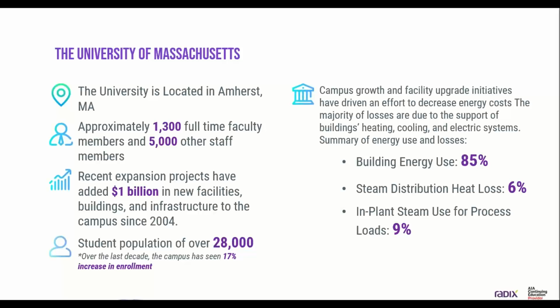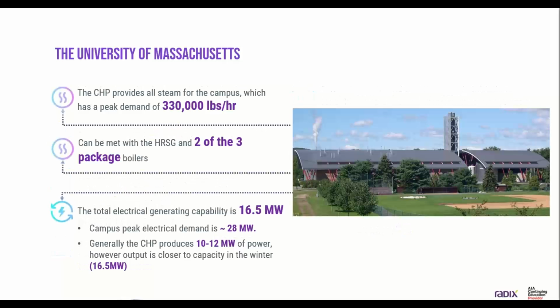So the campus growth and facilities initiatives have driven an effort to decrease energy costs. Major losses here are really due to the buildings on campus - heating, cooling, electrical systems. You can see building energy use is really 85%. Steam distribution losses are about 6%. We have 23 miles of steam and condensate piping out there on the campus, a lot of it in direct burial. And then we have in-plant use of steam for our deaerators and heat at the buildings, about 9% there.